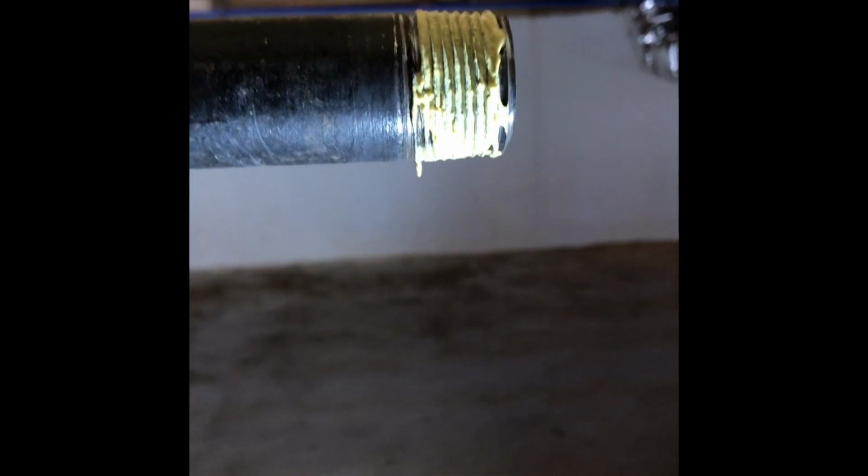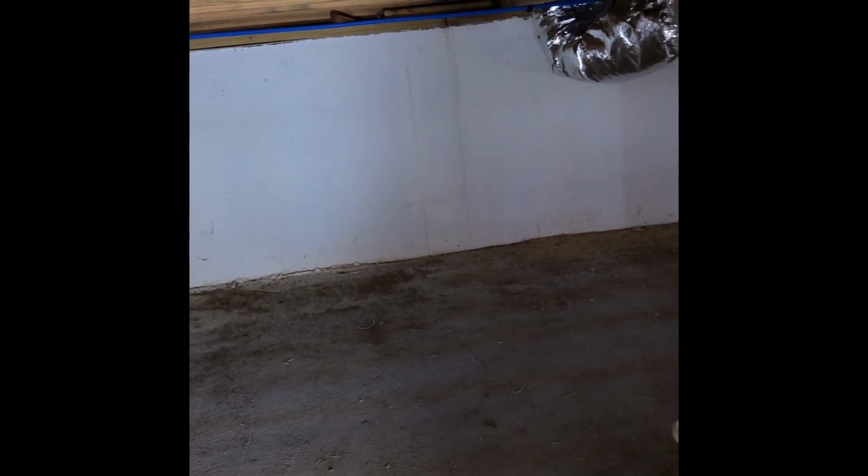Next thing I'm going to do is give them a good coat of Rector Seal. This is the yellow number 5. This is good for LP gas, natural gas, stuff like that. The inspector's probably going to want to see this yellow dope on there. I've got some new tape I'll show you in a minute. It's not yellow, but most of my other joints are yellow dope and yellow tape. So good old Rector Seal. Can't go wrong with this stuff.